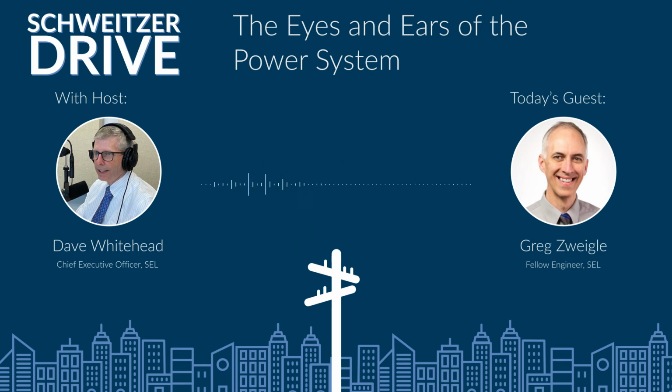Because there's a lot of inertia in the power system, and that inertia is coupled by long lines, things can start to get unstable, and they can start rocking more and more. Eventually that can cause big problems. This issue has caused major outages in the past. And so synchrophasors, because they're a really high-speed measuring technology, precisely time-aligned over a wide area, let us look at these oscillations. And SEL has developed some solutions around this to be able to control them and prevent outages that could happen if they start to go unstable.